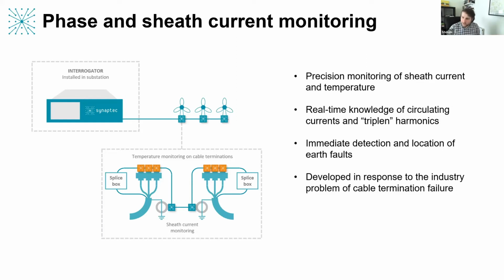One example is that we know it's important to monitor the continuity of the sheath to make sure it has a good solid earth connection. Typically it'll be earthed at both ends of the cable, and we can monitor that over time to make sure it's still connected. It's also very useful to have visibility of the circulating currents in the sheath in real time. Partly that's just for determining the ampacity of the cable, to enable better dynamic cable rating. So how much power is flowing and how much headroom there is for more power, because the currents flowing through the sheath will cause heat generation, which will impact the phase conductors as well. So it's useful to have that information.